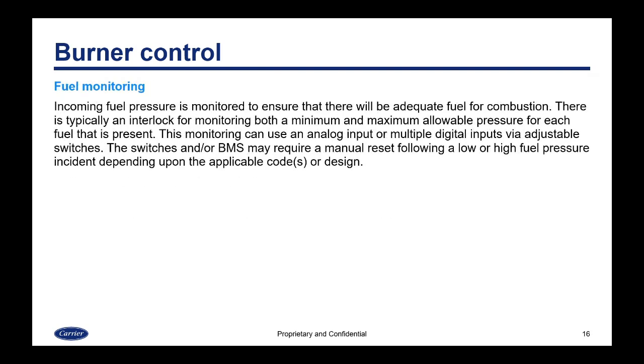Incoming fuel pressure is monitored to ensure there will be adequate fuel for combustion. There is typically an interlock for monitoring both a minimum and maximum allowable pressure for each fuel that is present. This monitoring can use an analog input or multiple digital inputs via adjustable switches. The switches and/or BMS may require a manual reset following a low or high fuel pressure incident, depending upon the applicable codes or design.